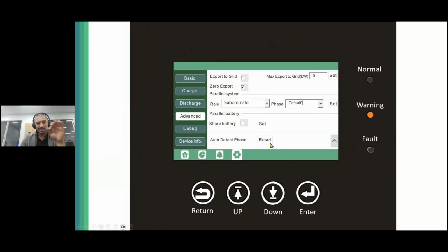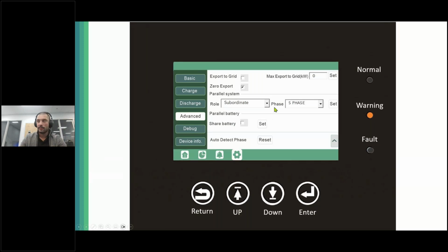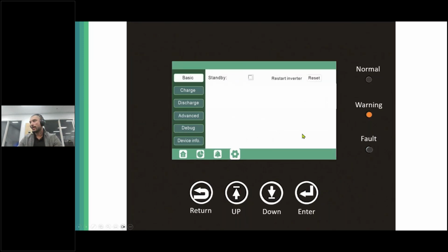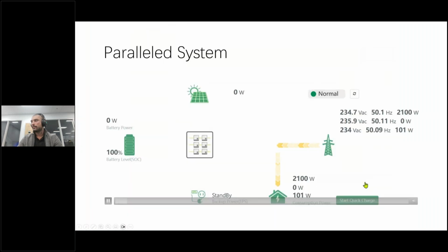In parallel systems, this is the first step you're actually going to do before anything else. This way, you've basically synchronized all inverters, and by programming the master, whatever information you put on the master is going to propagate to the other inverters. So you don't have to double or triple the work when programming the LCD. Then deselect standby. Essentially that's how it will look in the web portal or the LCD - you'll see the voltage on all three, the frequency on all three, and how it's working as one system.